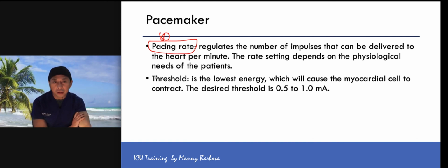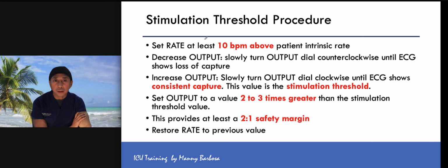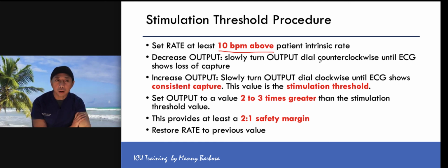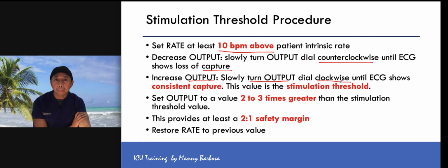But just to give you an idea, there is a threshold that you might hear, which is the lowest energy that will cause the myocardial cell to contract. And we always check for the thresholds. So stimulation threshold, you at least set the rate 10 below or above the patient's intrinsic rate. And you decrease the output by slowly turning the output counterclockwise until you lose the EKG for capture.